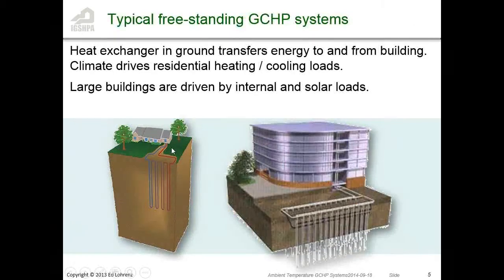Basically looking at one of the differences between individual heat exchangers for houses versus for commercial buildings: houses are typically driven by the climate as much as anything else. The occupancy is going to change it a little bit, but not anywhere near as much as with a commercial building. Here, each person is putting out about 200 or 400 BTU per hour, adding to the cooling load of this building. That's why buildings like this are often cooling dominant.